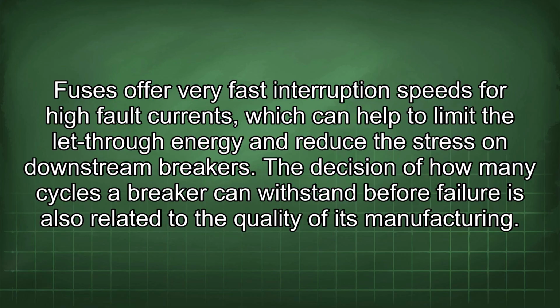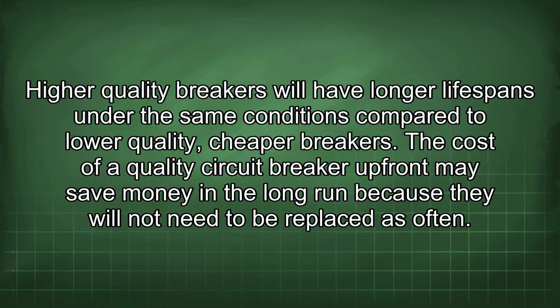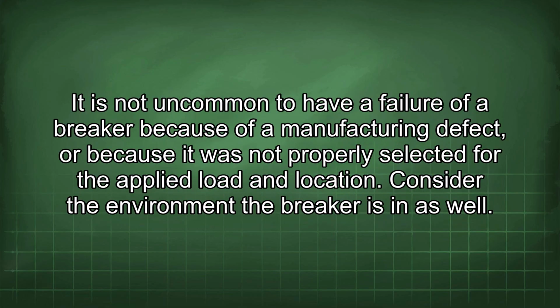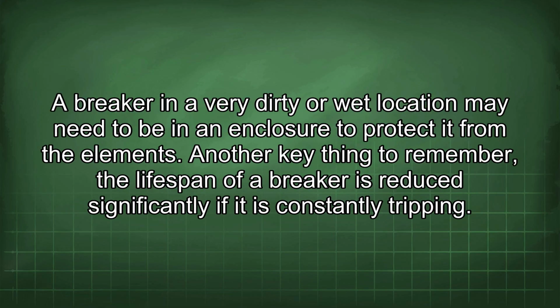The question of how many cycles a breaker can withstand before failure is also related to the quality of its manufacturing. Higher quality breakers will have longer lifespans under the same conditions compared to lower quality, cheaper breakers. The cost of a quality circuit breaker upfront may save money in the long run because they will not need to be replaced as often. It is not uncommon to have a failure of a breaker because of a manufacturing defect or because it was not properly selected for the applied load and location. Consider the environment the breaker is in as well. A breaker in a very dirty or wet location may need to be in an enclosure to protect it from the elements.